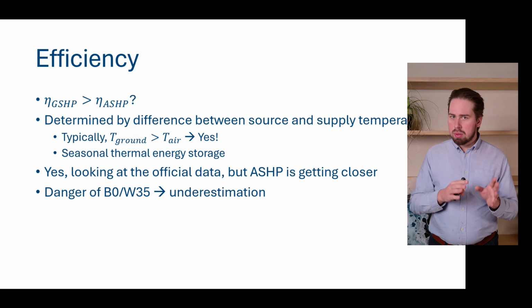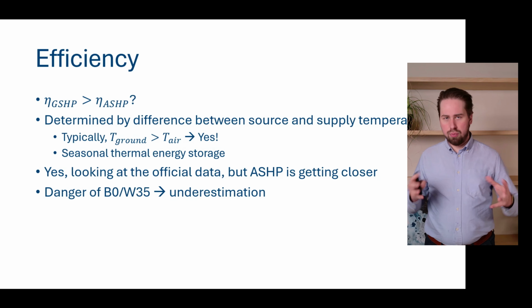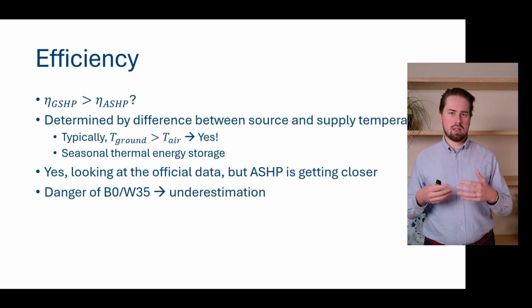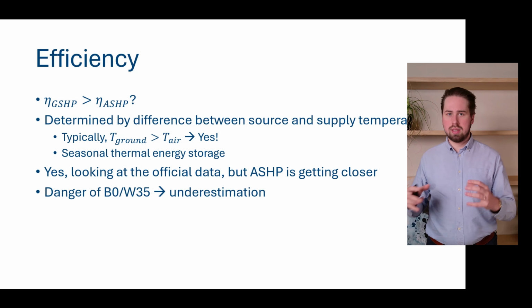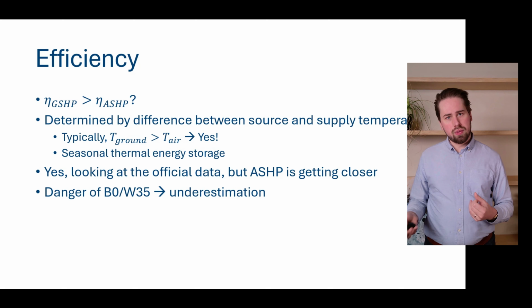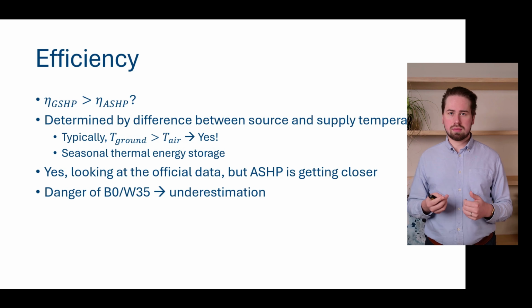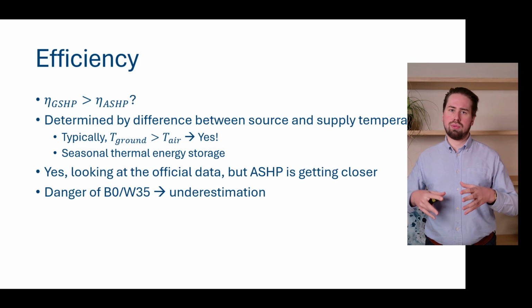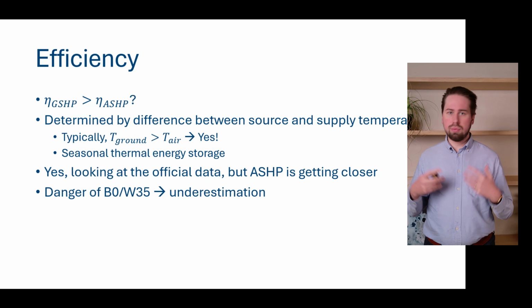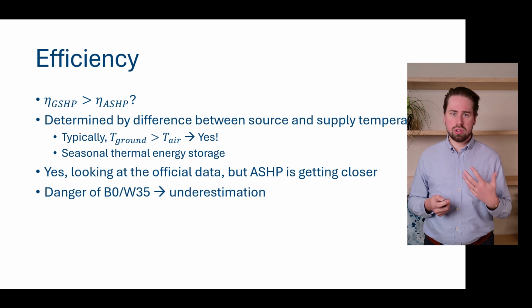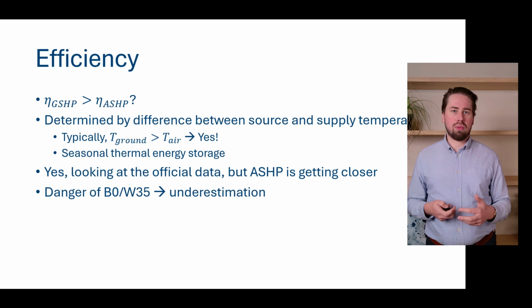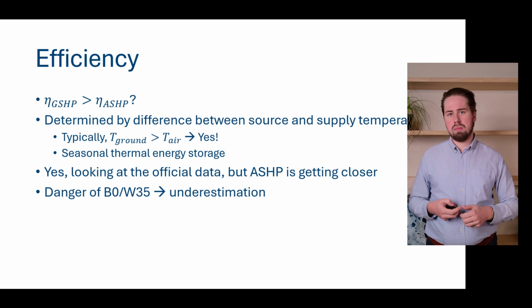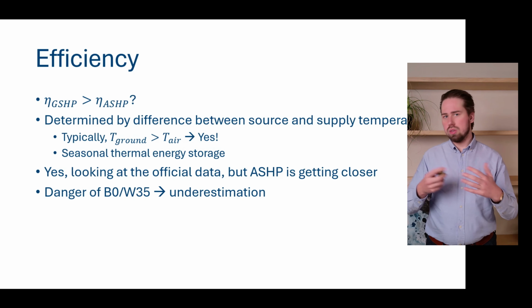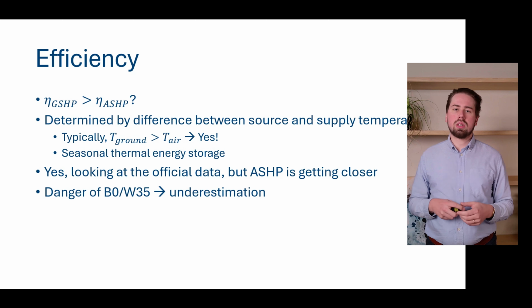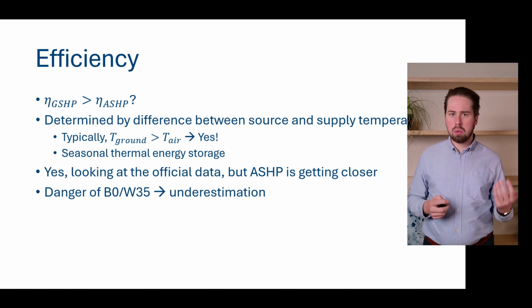Now, there is a problem on paper, because typically the efficiency of a ground source heat pump is given at B0W35, meaning 0 degrees coming out of the ground and 35 degrees going into the building. But this is typically an underestimation of the borefield temperatures. If you design your borefield accurately, these 0 degrees will perhaps be reached only after a couple of years and only at the peak moment, the most critical moment in the year, not on average. So that's also a little bit of vagueness there, which we will shine some light on in a couple of next chapters.